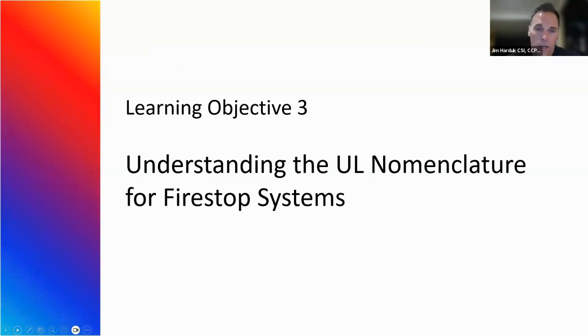So we talked a little bit about why we firestop, and we talked a little bit about the testing that's involved with these firestop systems. So what I want to talk about now is the UL nomenclature. Basically, all of these firestop tests are conducted by an independent third-party lab. And since UL is the most recognizable one, I'm going to focus on that now. I also want to note that probably about 95% of all of 3M's through penetration firestop systems are UL tested systems. So that's why I'm focusing on that right now. So next slide, if you would.